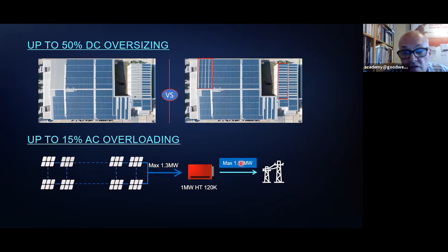So in this example here, you can see we've got a 1 megawatt system comprising the 120k HT. Well, if you oversize that by 30%, so we're showing here a 1.3 megawatt input to this inverter, we can actually achieve on the output 1.15 megawatts. So that's a 15% AC overloading. So if it was just 1 megawatt, we just have 1 megawatt out.